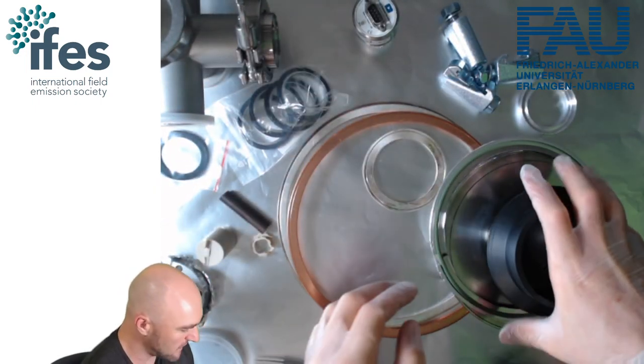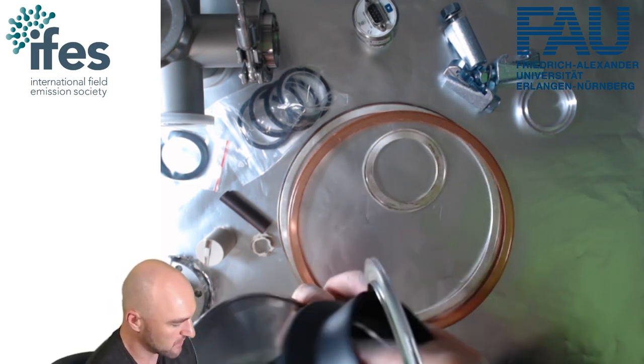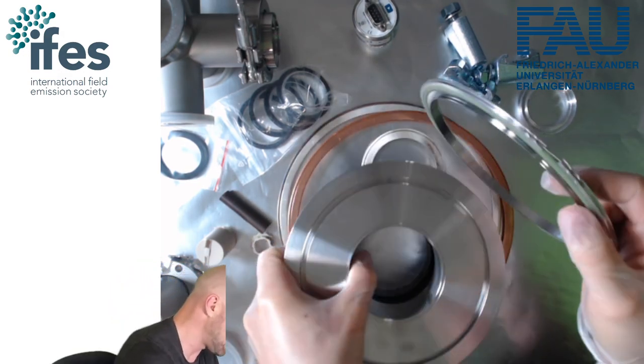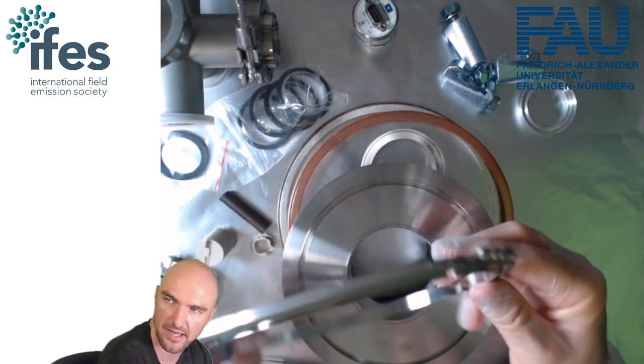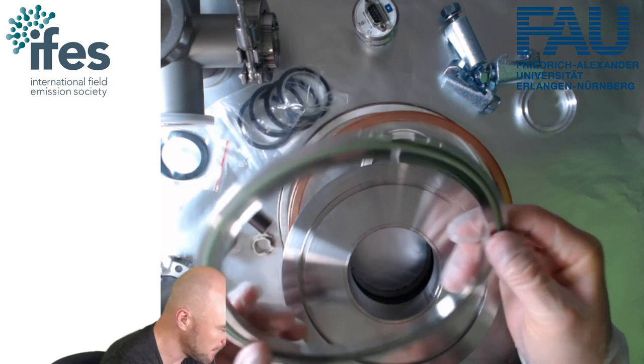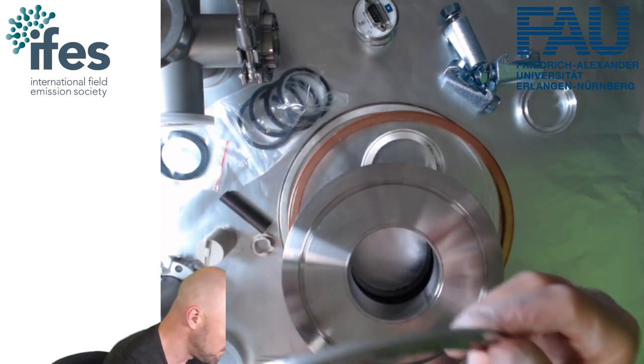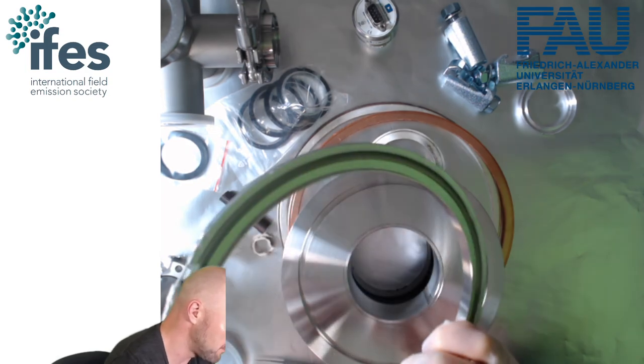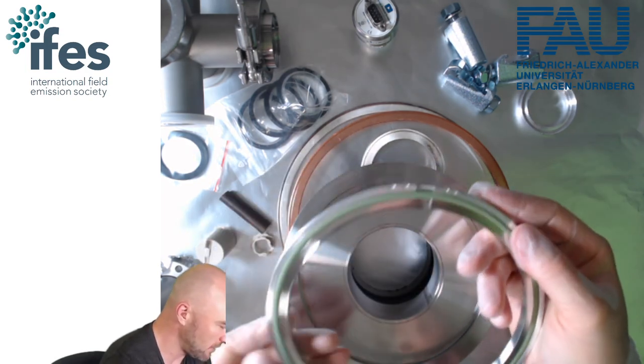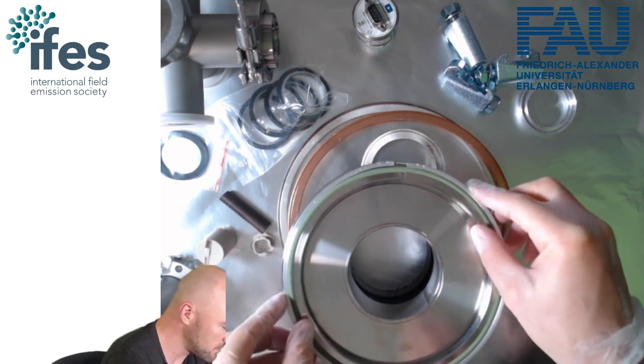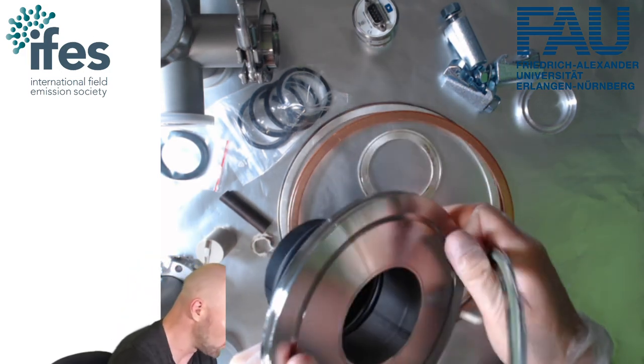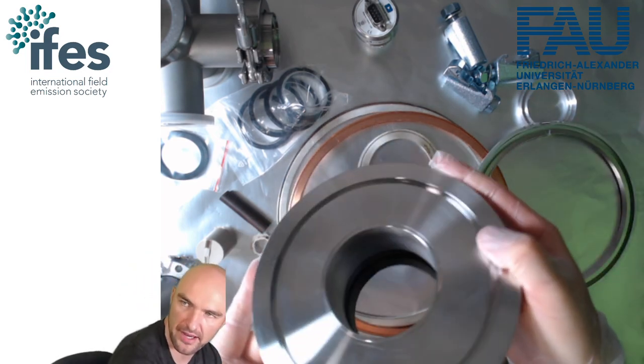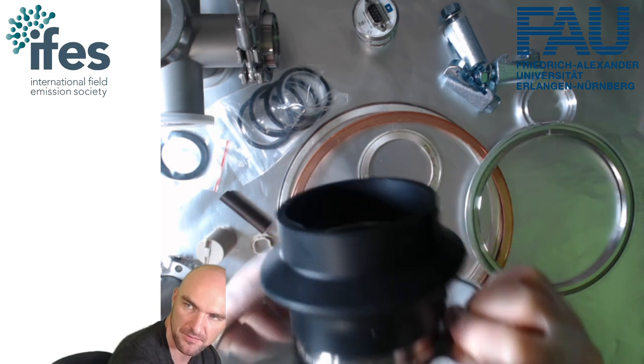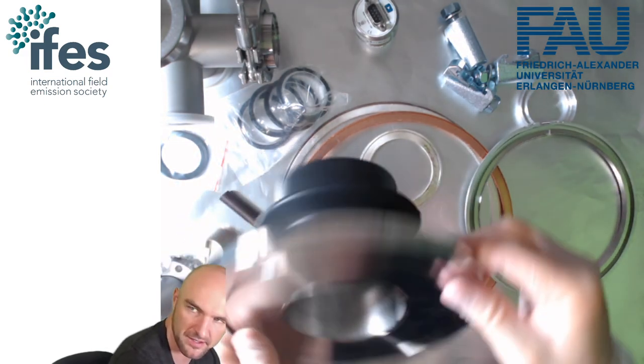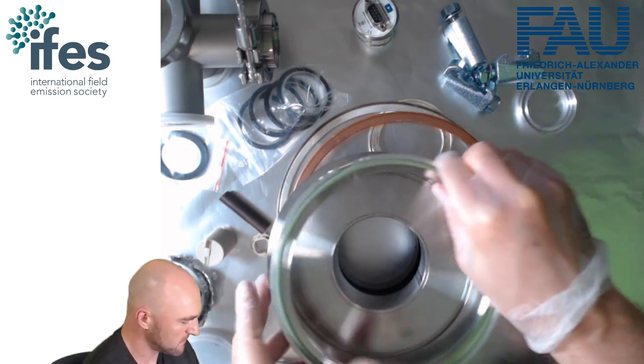If you have a high vacuum flange and you need to go larger than that, what we use are so-called ISO K flanges and ISO F flanges. They're related, and essentially you have some kind of seal like this here. This is actually part of the cryo interface of one of our atom probes. You can see you have some kind of ring that holds everything stable, and it puts it into a groove here in the actual vacuum part. And then you have some kind of lip at the back of it that you can use to tighten the whole system.